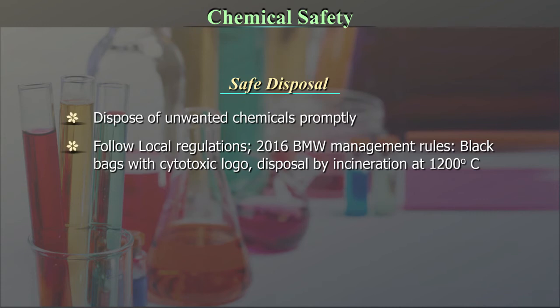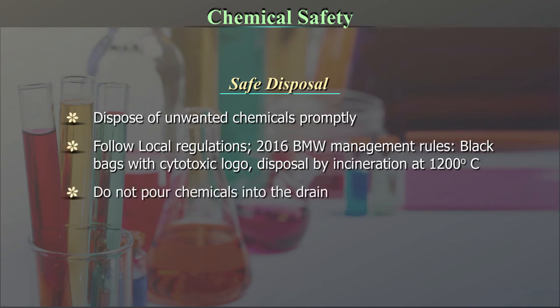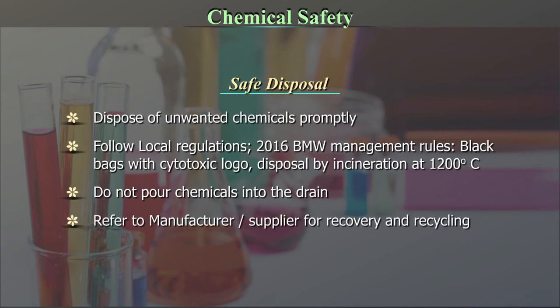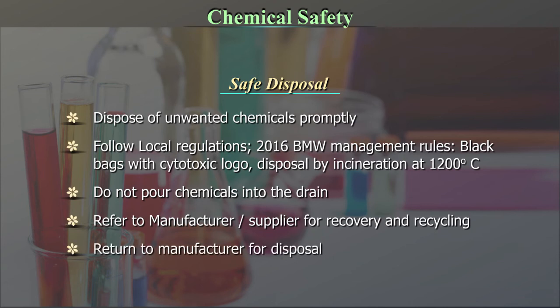Safe disposal: dispose of unwanted chemicals promptly. Follow local regulations, including the 2016 BMW management rules. Use black bags with cytotoxic logo and dispose by incineration at 1200 degrees centigrade. Do not pour chemicals into the drain. Refer to the manufacturer or supplier for recovery and recycling, or return to the manufacturer for disposal.